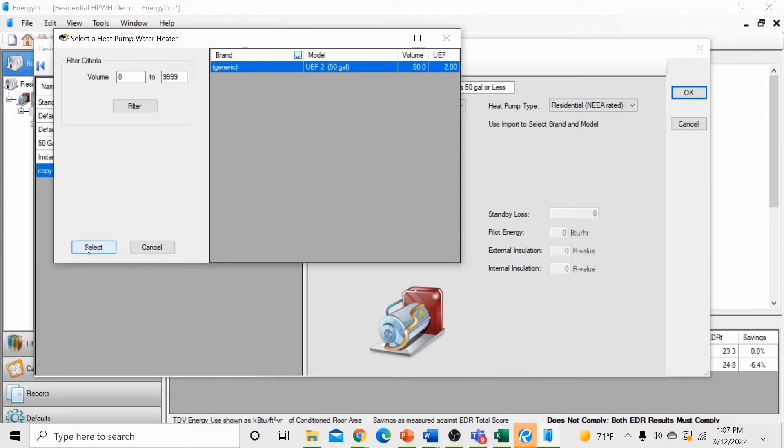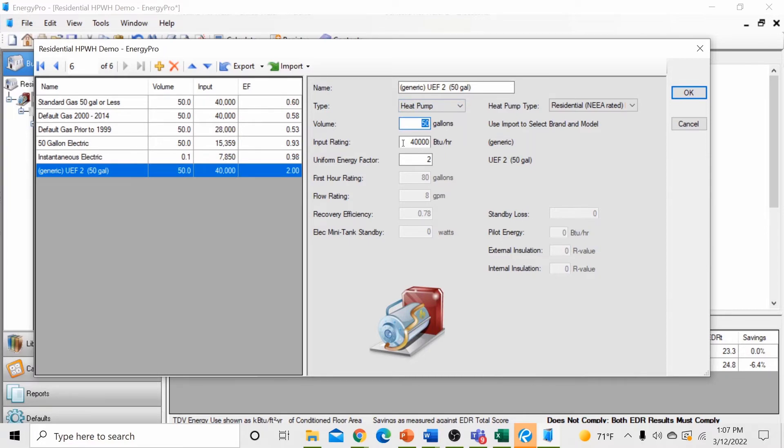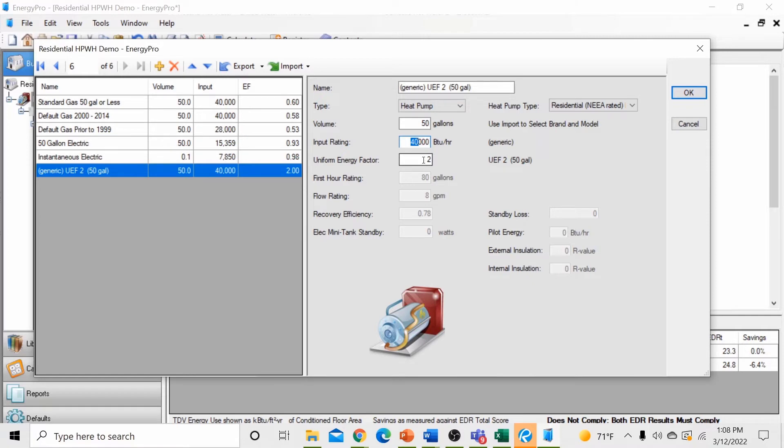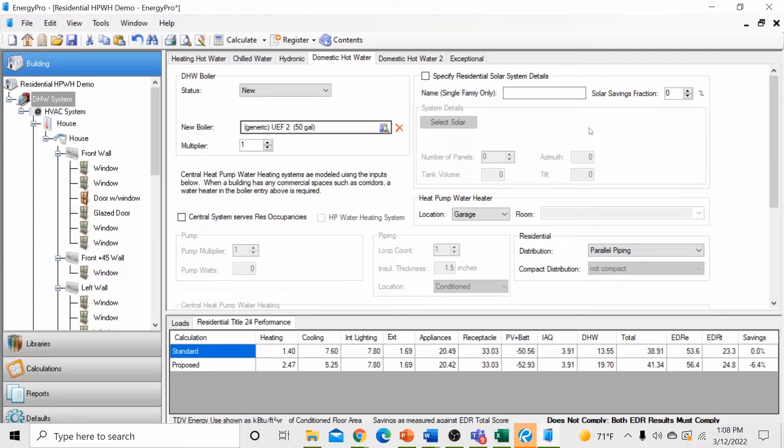Hit the select button and this will populate not only the name but also the characteristics of that generic UEF 2.0 50 gallon heat pump water heater. The gallons are equal to 50 gallons of volume. The input rating currently anything less than a 12 kW water heater would be allowed to use as a generic heat pump water heater. For this illustration, we're leaving the input at 40,000 BTUs. Additionally, the uniform energy factor has already been set for us at 2.0. Hit the OK button and you've just created a generic UEF 2.0 heat pump water heater which is equal to the standard design heat pump water heater when modeling new construction.